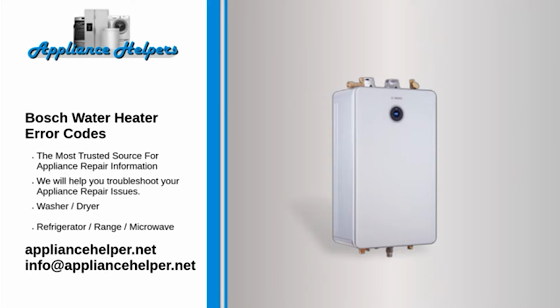Code A7. Problem. Outlet temperature sensor fault. Fix. The outlet temperature sensor reacts when the temperature is either below 36 F when the unit is protected from freezing temperatures, or above 210 F in a case of overheating due to the limescale deposits. Check the sensor and wiring. You might have to flush the unit to remove the mineral buildup.